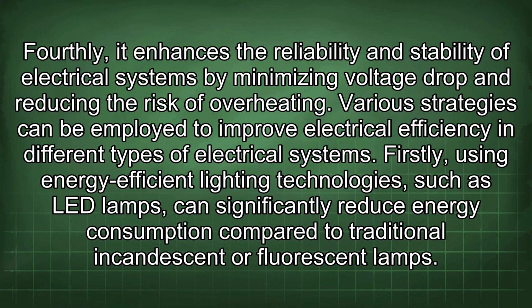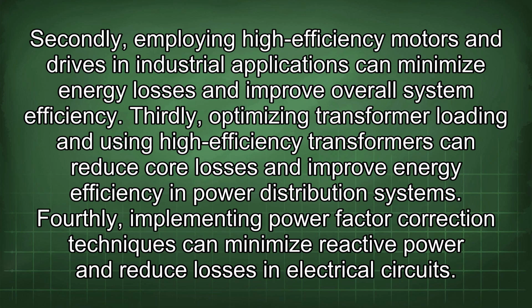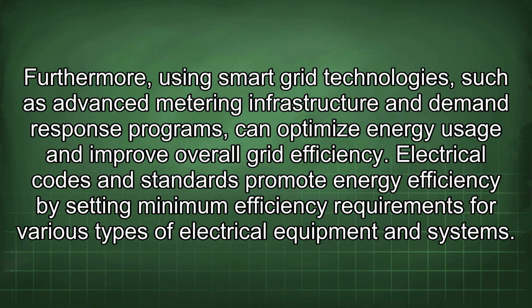Various strategies can be employed to improve electrical efficiency in different types of electrical systems. Firstly, using energy-efficient lighting technologies, such as LED lamps, can significantly reduce energy consumption compared to traditional incandescent or fluorescent lamps. Secondly, employing high-efficiency motors and drives in industrial applications can minimize energy losses and improve overall system efficiency. Thirdly, optimizing transformer loading and using high-efficiency transformers can reduce core losses and improve energy efficiency in power distribution systems. Fourthly, implementing power factor correction techniques can minimize reactive power and reduce losses in electrical circuits. Furthermore, using smart grid technologies such as advanced metering infrastructure and demand response programs can optimize energy usage and improve overall grid efficiency.